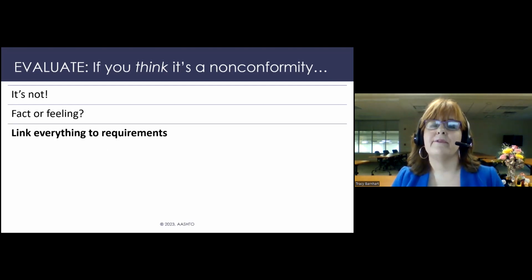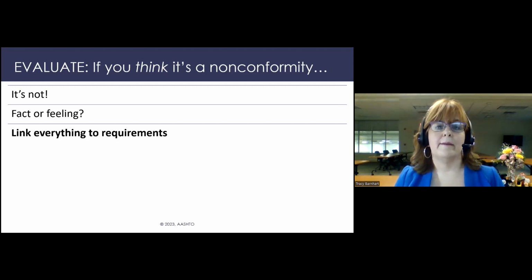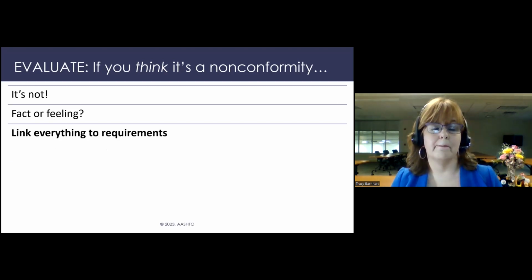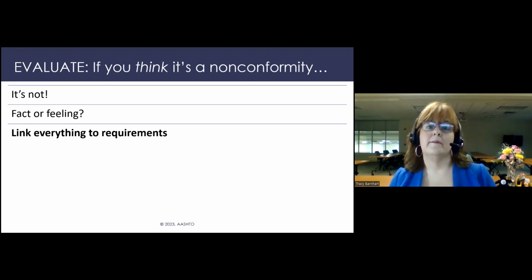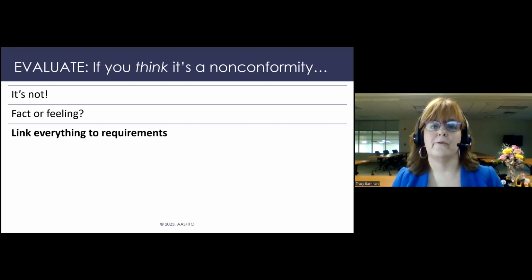You have to link everything to a requirement. If there's a requirement for it, great, then that can be a nonconformity. If there's no requirement, and let's say people are using pencil in the lab and you want them to be using pen, but there's no requirement to use pen, it's not a nonconformity. That can be an improvement opportunity, but not a nonconformity. It doesn't matter what you think.